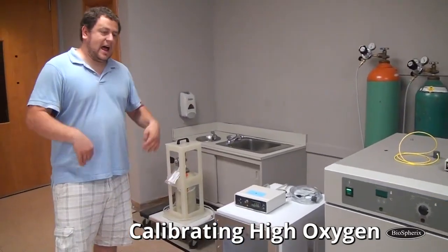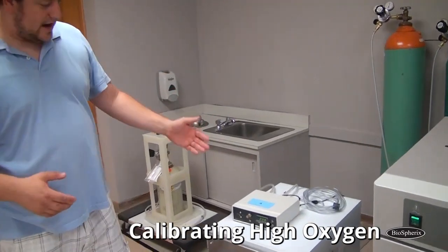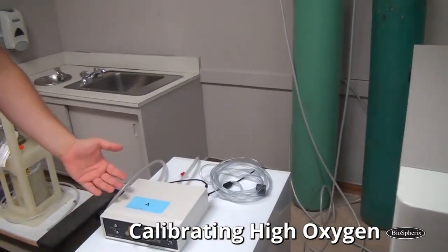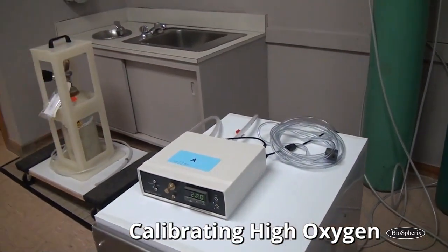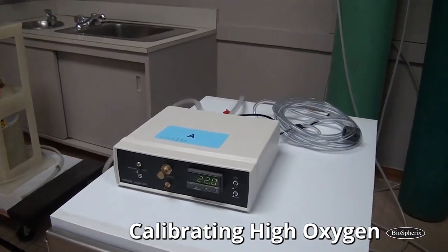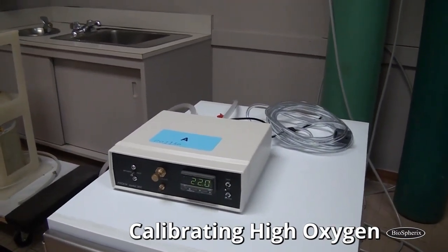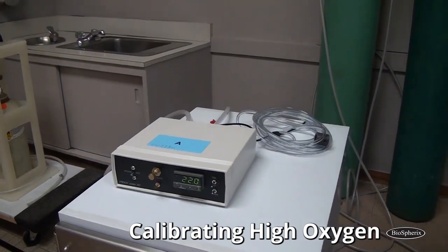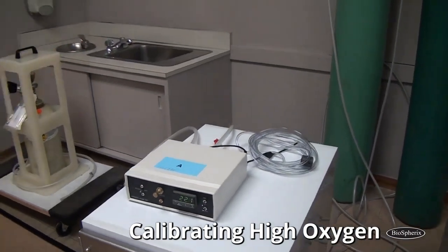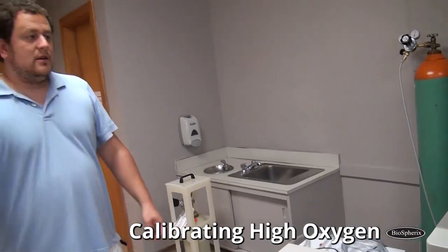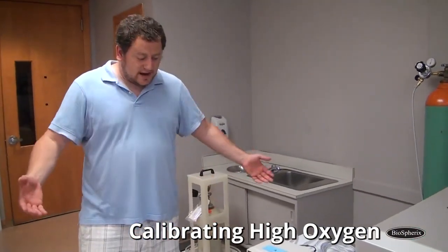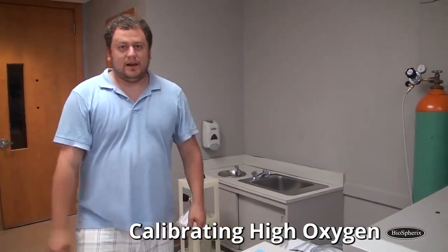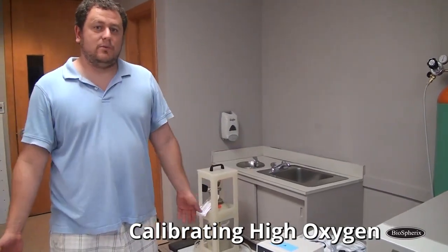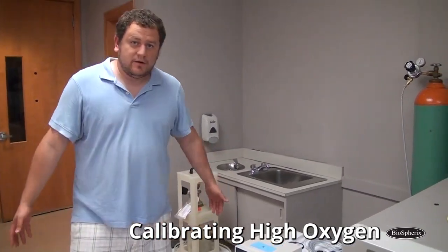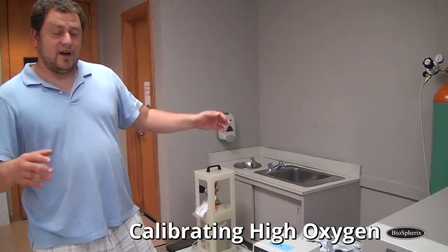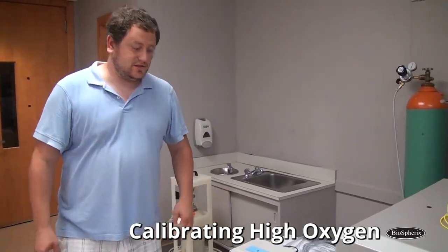So the difference, if you're doing high oxygen work, anything over ambient, you've got pure oxygen hooked up to your controller. You need to do a 0 and a span, 2-point calibration always. Difference is your known gas is 100% oxygen. The other gas you're going to have always access to is your room air, 20.8. So we're going to use 20.8 as our 0 in this case. If you have oxygen hooked up, use 20.8 as your 0.